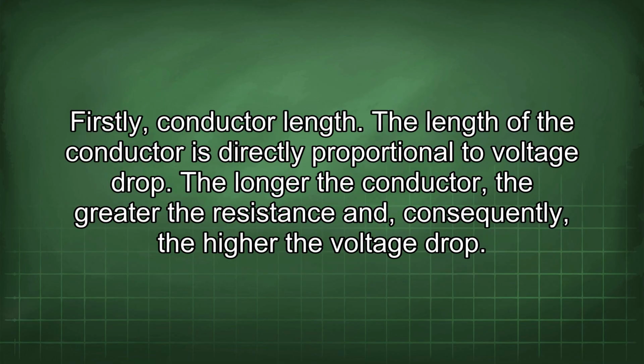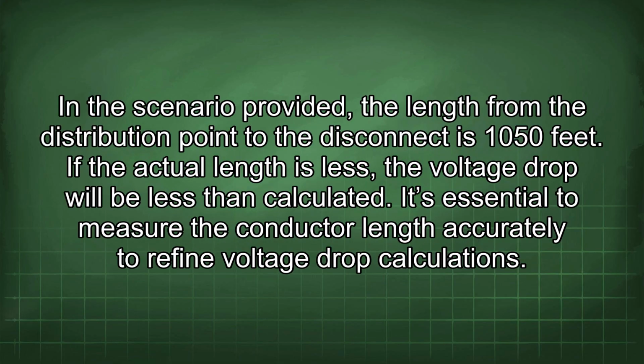Firstly, conductor length. The length of the conductor is directly proportional to voltage drop. The longer the conductor, the greater the resistance and, consequently, the higher the voltage drop. In the scenario provided, the length from the distribution point to the disconnect is 1050 feet. If the actual length is less, the voltage drop will be less than calculated. It's essential to measure the conductor length accurately to refine voltage drop calculations.